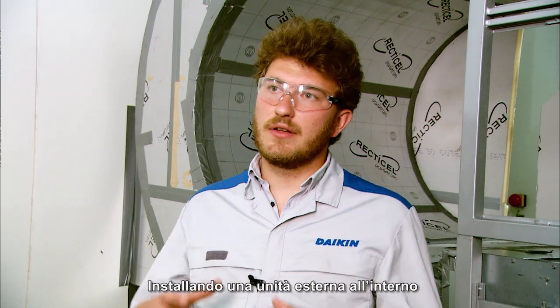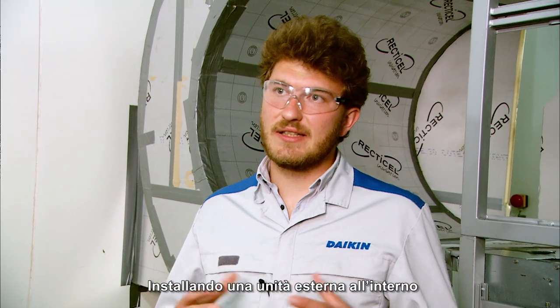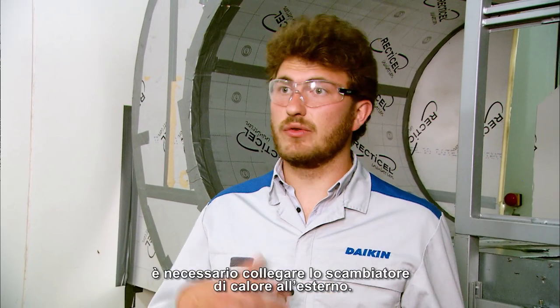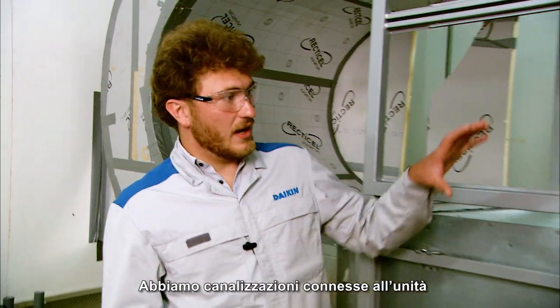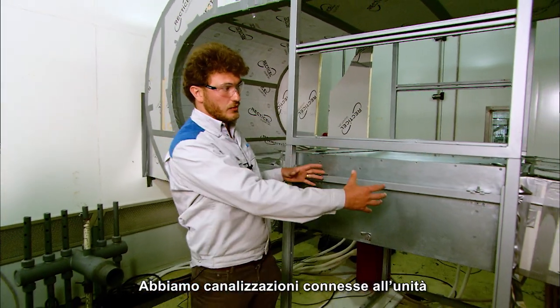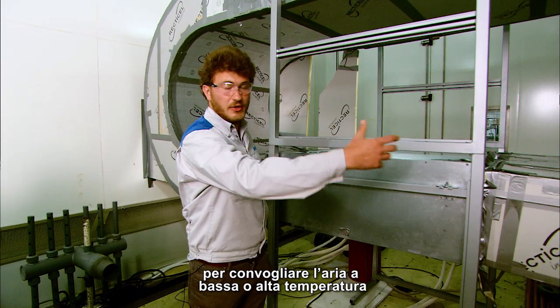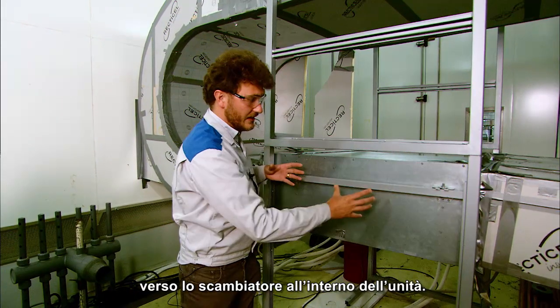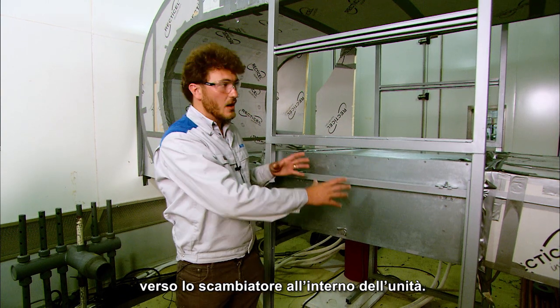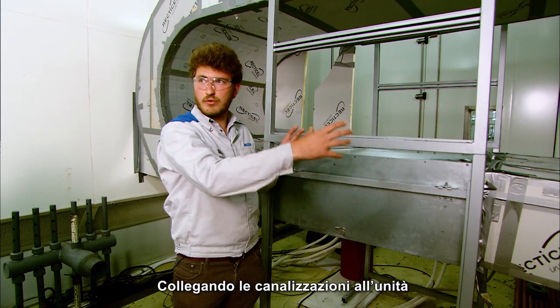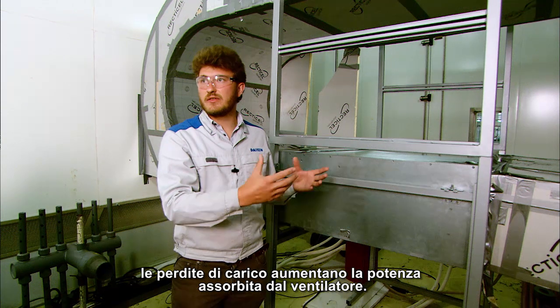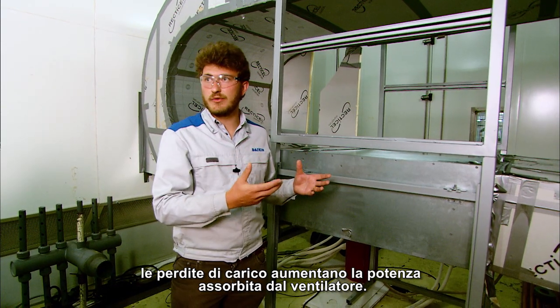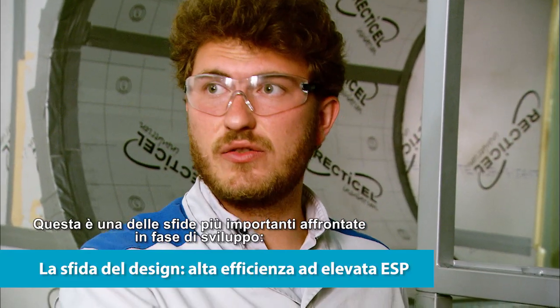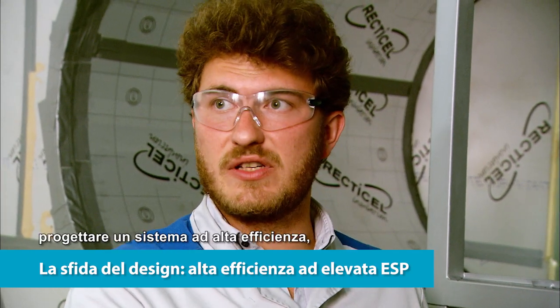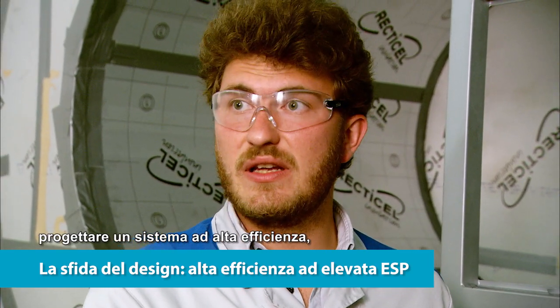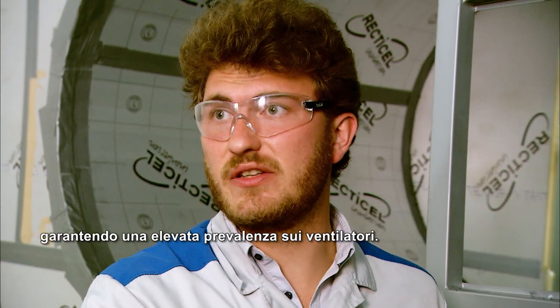By installing an outdoor unit indoors, it's necessary to connect the heat exchanger to the outdoor air. We have ducts connected to the unit to connect the low temperature or high temperature air with the heat exchanger within the unit. By connecting these ductworks to the unit, the frictional losses of the air increase the fan power input. This is one of the main challenges we had for this development: to design a unit with a high efficiency even in these high static pressure situations.